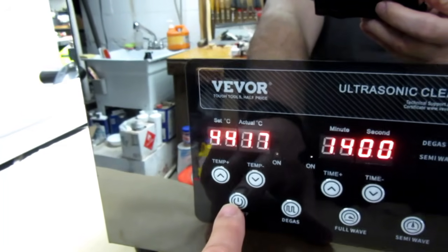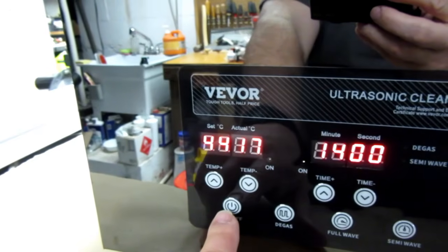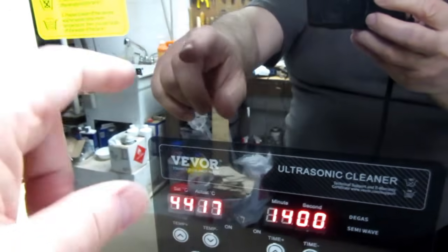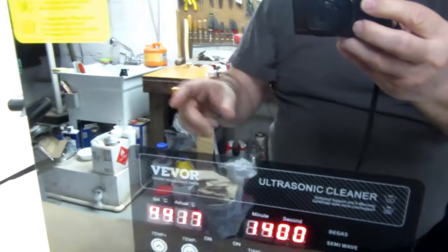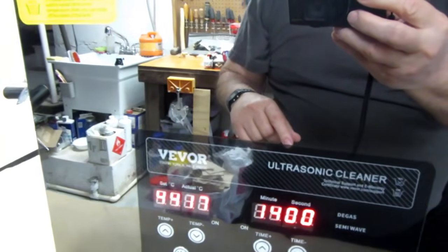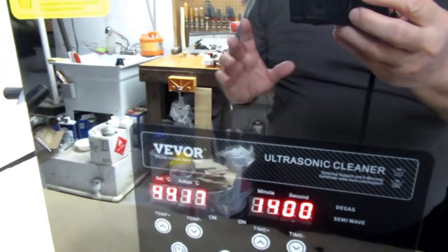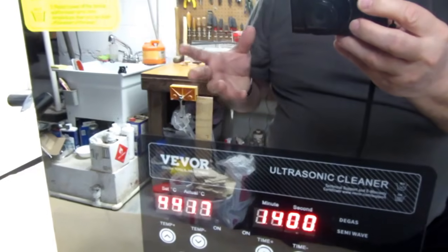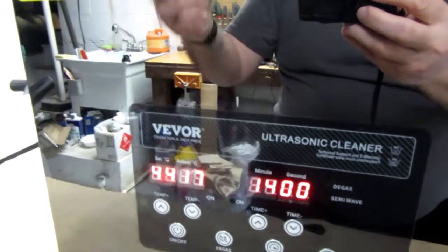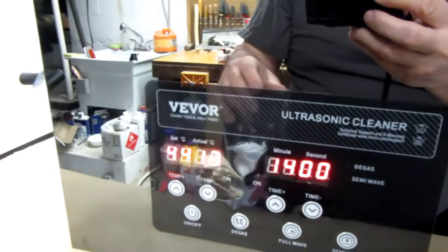This is a point I should mention that I forgot earlier: never ever run an ultrasonic cleaner with nothing in the tank. It will destroy it. The transducers get hot and they lose their heat through the tank into the fluid, acting like a heat sink.